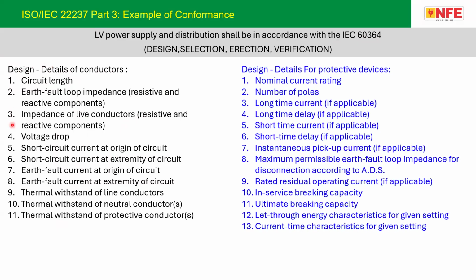Similarly, when you select the protective device, serial number 1 to 13: nominal current rating, number of poles, long-time current, long-time delay if applicable, short-time current, short-time delay, and the final one, current-time characteristics for given setting. All these subjects are to be considered in the design if you want to comply with 60364, and what is written is that it shall be complied with. So you must consider these points. Also, the concept followed in 60364 is design, selection, erection, and verification. First is the design, then selection of the equipment to be used, erection of the equipment, and finally verification.